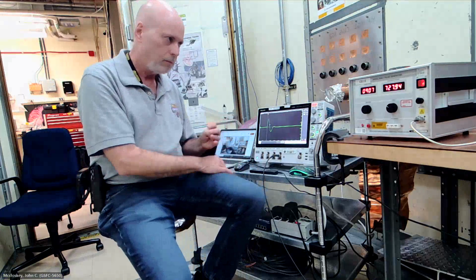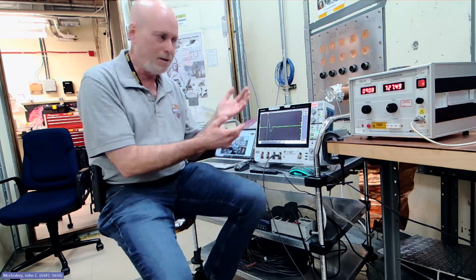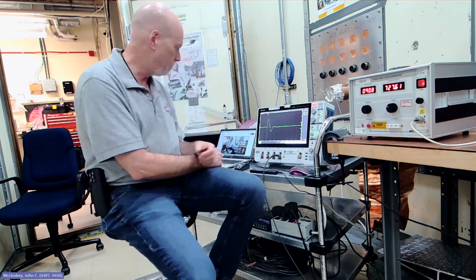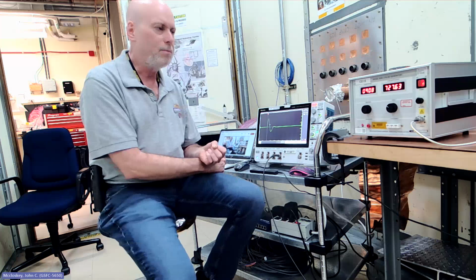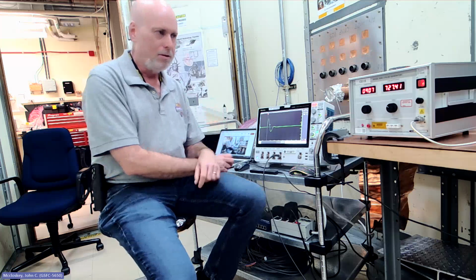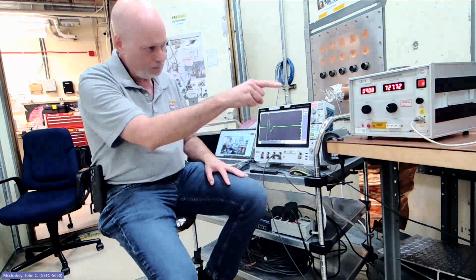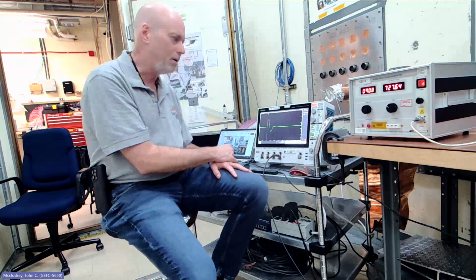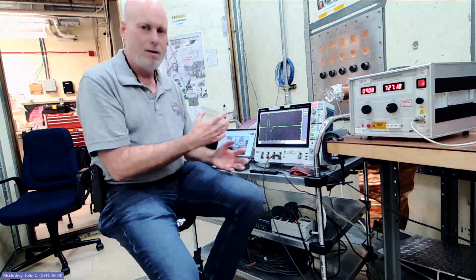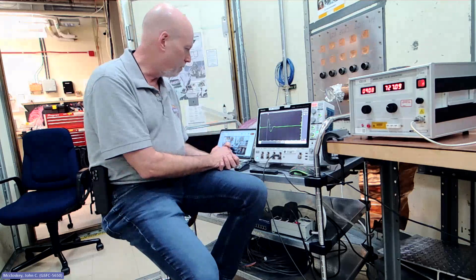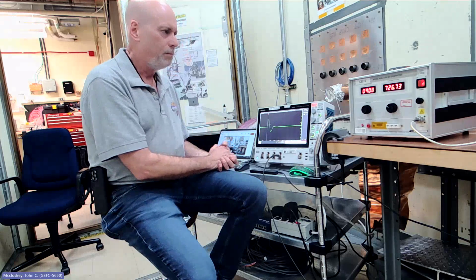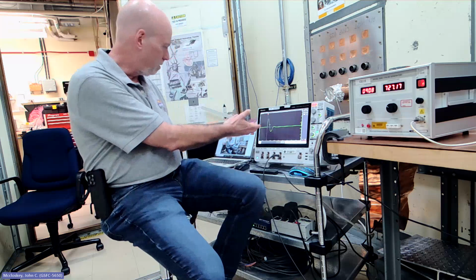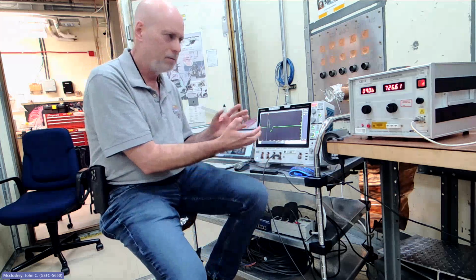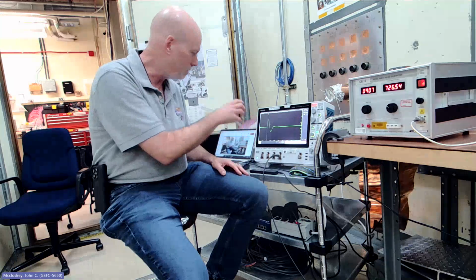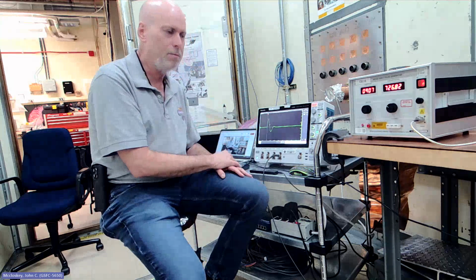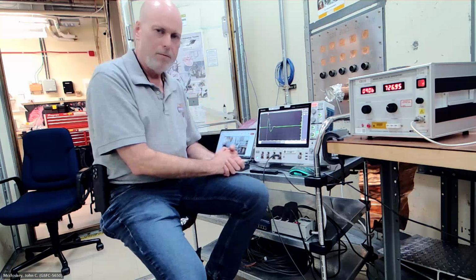All of these test methods have their nuances, but CS115 is something of a nuanced test method. If you're not used to it, things can look a little weird. Even the jagged nature of the signal on the waveform that you get out of the cal fixture can be a little disconcerting if you haven't seen it before. And then you see this, and it's like, well, what happened to my nice clean waveform? Well, that's okay. You're getting the response of your cable to that stimulus. So that's what I wanted to show you.